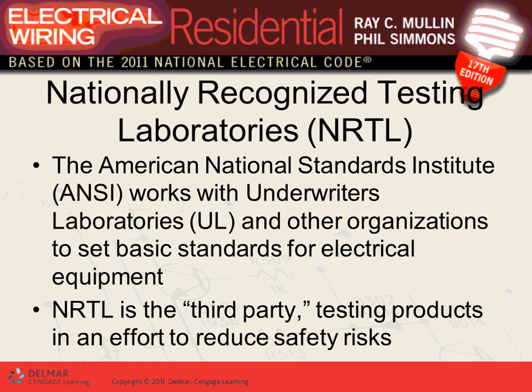You can say anything about yourself, but I need third-party verification. Give me a respected organization, not just the manufacturer, that verified you're the best. That's how NRTLs work, like UL. They're a respected organization that can verify what you say is actually true, because you can't take the word of the manufacturer about their own equipment. That's not enough. It's a check and balance, like in government. Somebody has to check you who has no interest in your product.